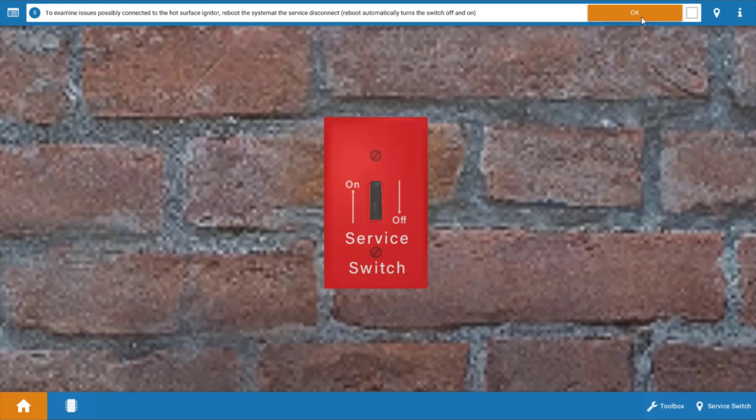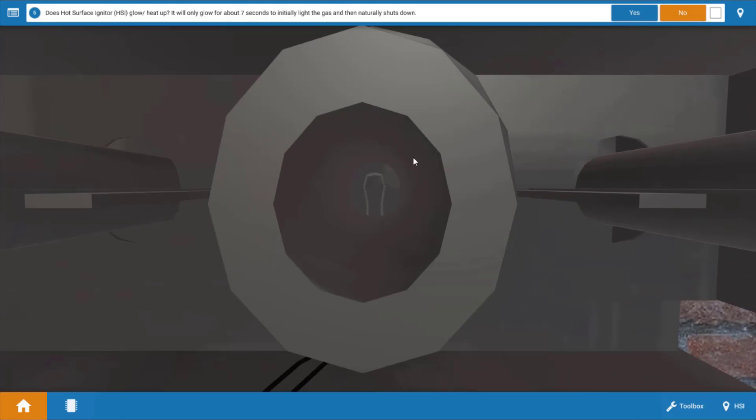Now you want to be ready because immediately you're going to have to start looking for that igniter glow. So when we go down here we look the igniter's here in the back and there's no glow coming from it. This thing actually will reach surface temperatures of 2600 degrees so there'd be an obvious orange glow there. So no our igniter's not on.